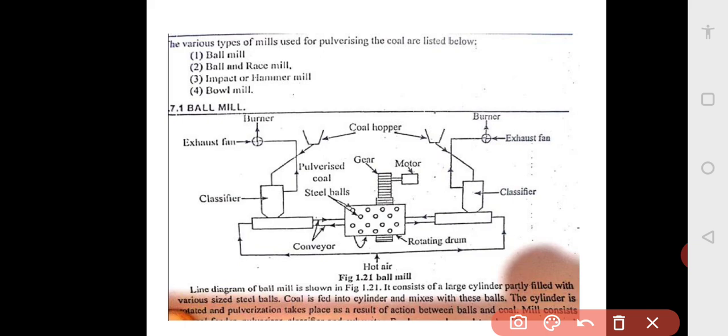The output of the mill is controlled by dampers located at the exhaust fan inlet duct. These dampers vary the flow of air through the mill and thereby control the rate of fuel removed from the mill. The feeder output is regulated by the coal level in the cylinder. When the coal level in the cylinder attains sufficient height to seal the lower channel, then the differential control operates to stop the coal feed.